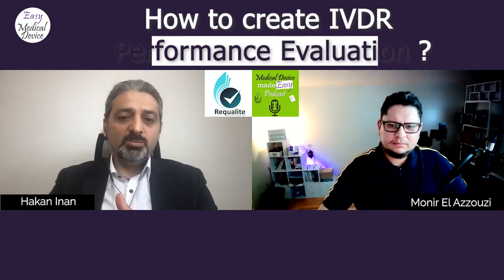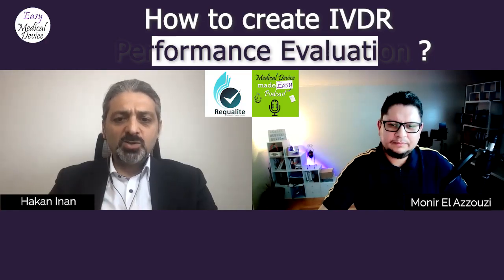Yeah. And also, just keep in mind, Munir, this was for the directive, published in 2012, if I'm not mistaken. So it is as per the directive. Yeah. But still, I think that's the gold standard that at least gives us information about how to perform certain parameters, like how to demonstrate scientific validity, and how to perform the literature search. Because the literature search needs to be methodological, and protocols have to be provided. We have to follow certain protocol, certain methodology, and this has been well described in MedDev.